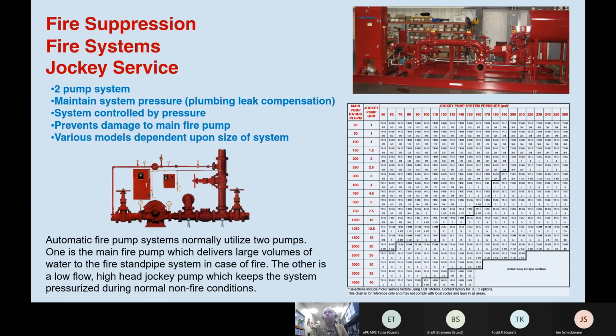So anyway, the fire suppression systems, like I had mentioned earlier, the jockey pump systems on our website, and I'm still working on it. It's about halfway done. It's on my list of goals to get done this year. If you go to our website, you can see that we have a jockey selection chart that, when you choose the main pump rating of the fire system and the main pressure of the pipe system, you'll get an exact selection for your pump.